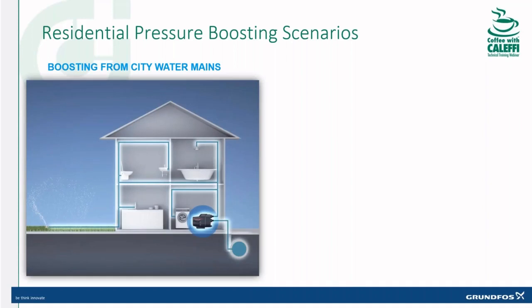Okay. So residential systems, let's switch gears for a moment. We have many scenarios where you might need a residential booster. The two main ones: first, sometimes you just don't have enough pressure and you want a little more, maybe you've got some of those nice multi-head showers that use a significantly higher volume of water, or maybe just a large family, a lot of kids taking a bath at the same time, simultaneous usage. So basically a residential booster is going to give the owner more pressure, but it's not going to give you more hot water. That's a different webinar.